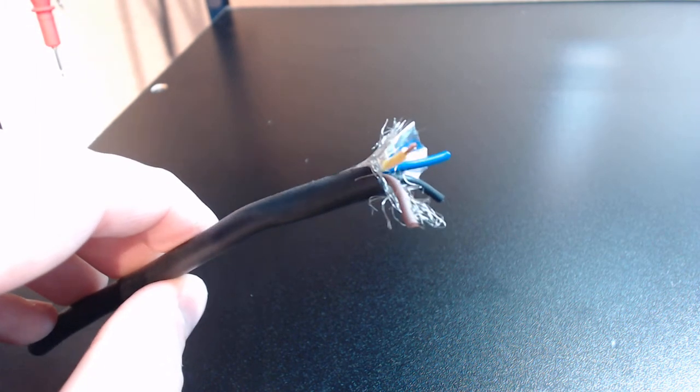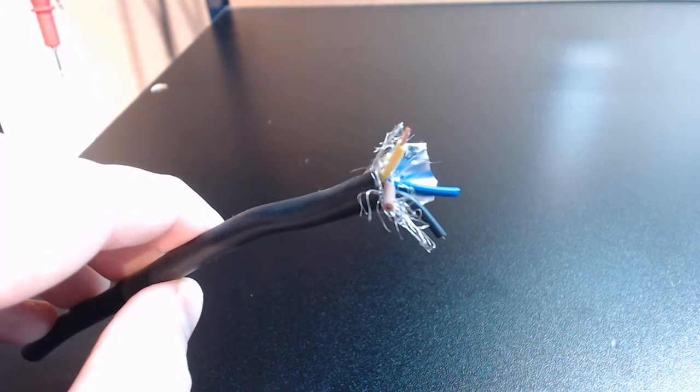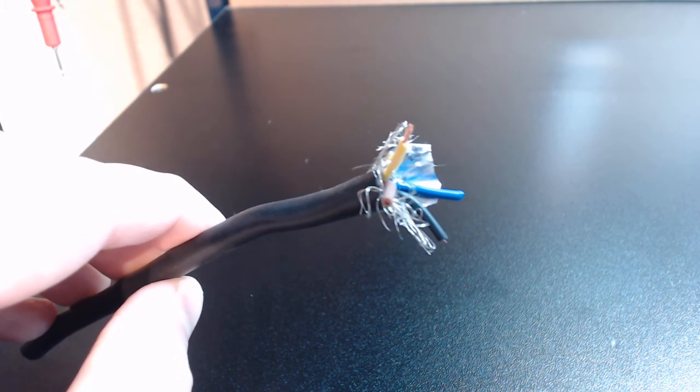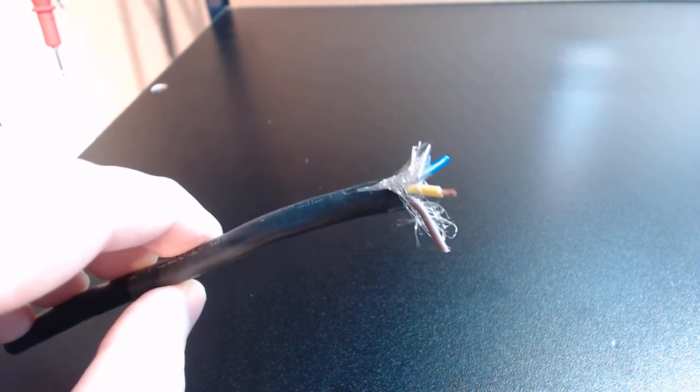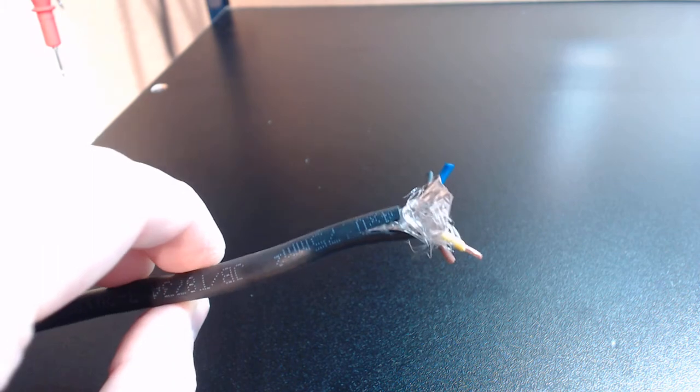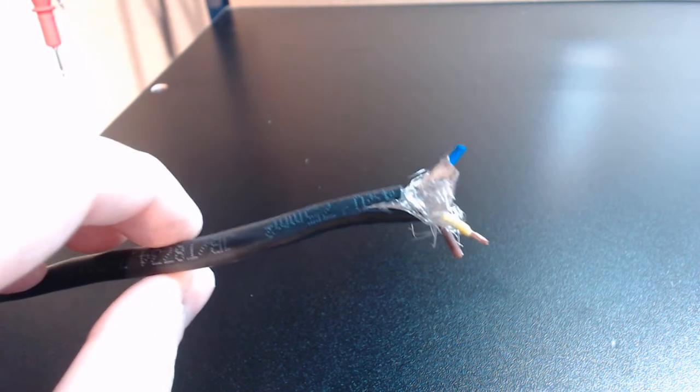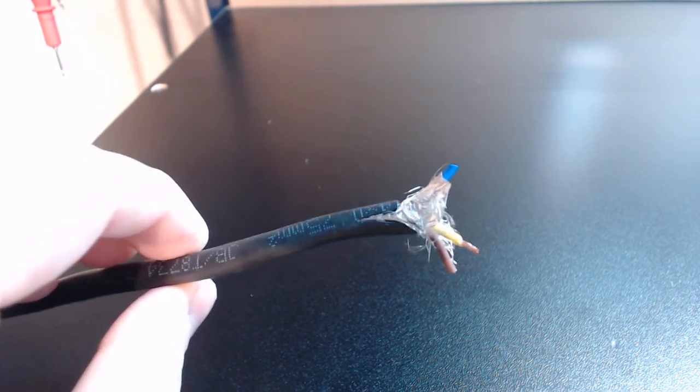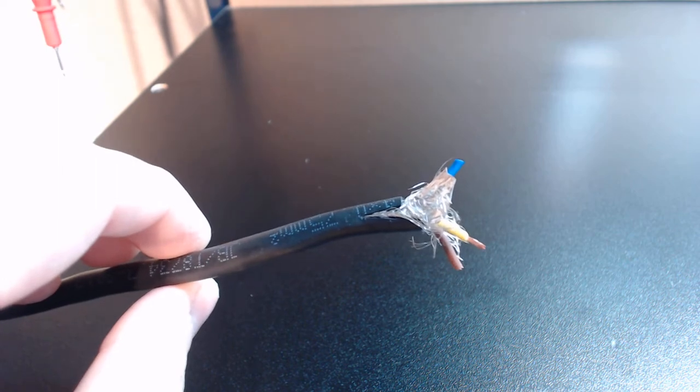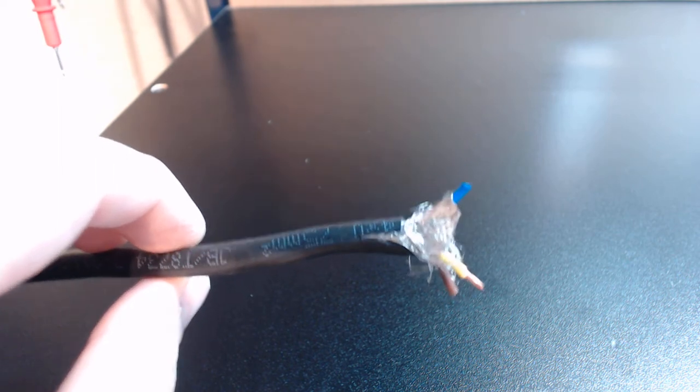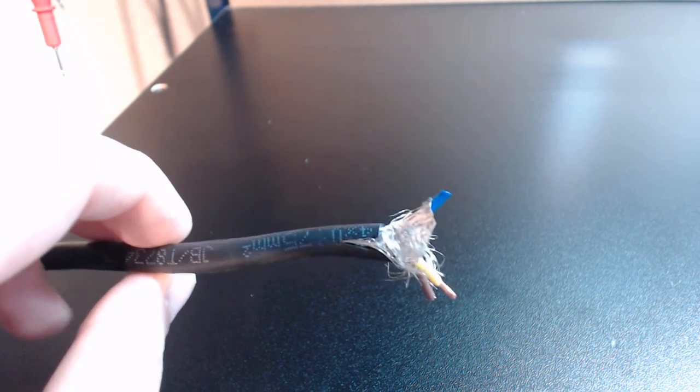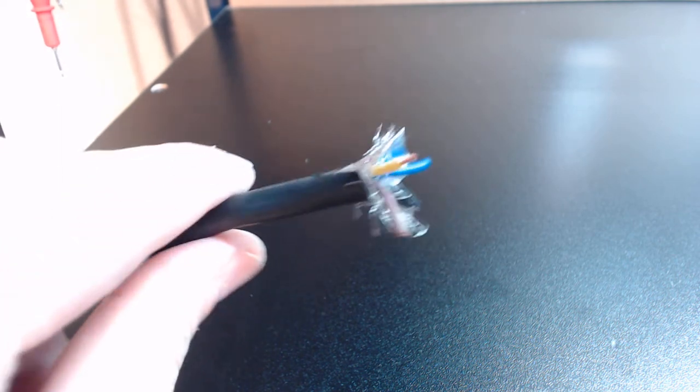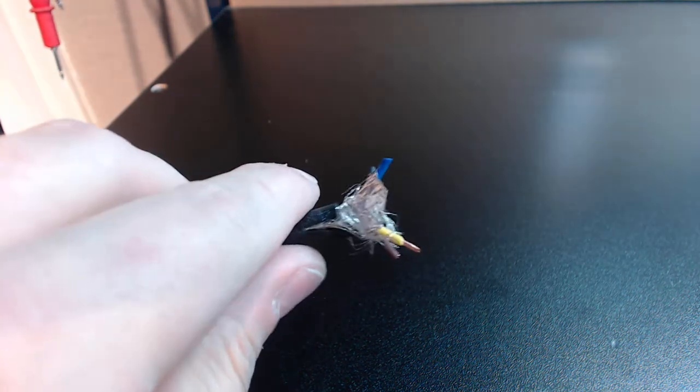Or lack the flexibility that we require with our systems. If you guys are trying to build a system that's virtually bulletproof from EMI and you're in a noisy environment, this cable will definitely eliminate virtually all your EMI issues, whatever is connected to the end of it, pending of course you terminate the shielding properly and ground it properly.